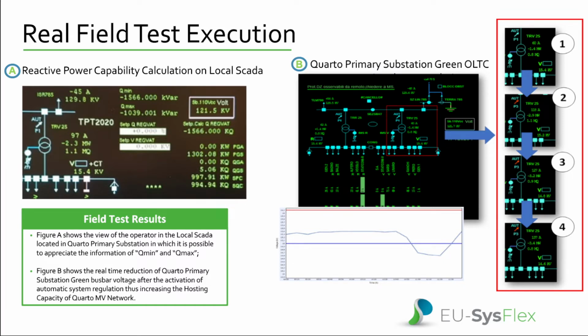In the right part, it is possible to see an overview of the central SCADA, in which it is possible to see the variation of the voltage on the bus bar of one transformer, the green transformer as the Enel convention. And so we have the shape of the voltage during the running of the test. The lowest value that is highlighted in blue in the picture of the voltage is about 15 kilovolts.